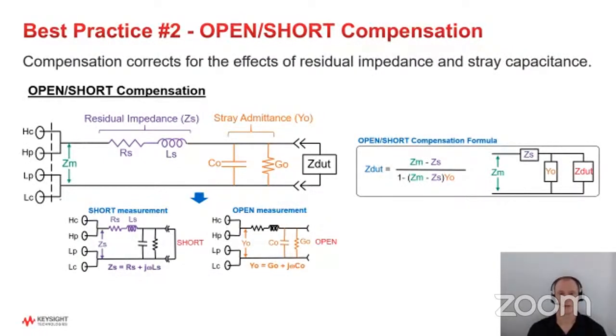The other thing you need to do with the cables, besides, of course, using the proper type of connections for the cables, is at a bare minimum on a capacitance measurement, you really need to do open short compensation. And all capacitance meters basically have this capability built in, as well as the ones we have for our B1500 series. It just means simply that you're going to have the cables going out to your DUT.